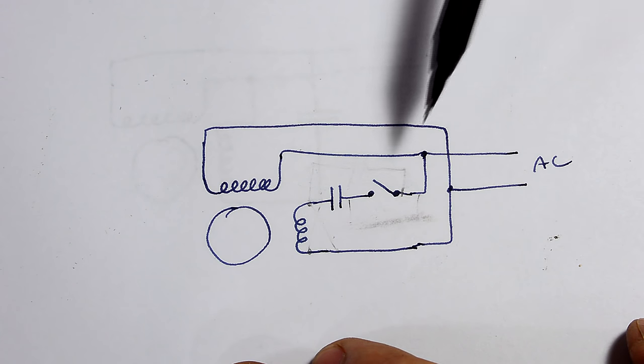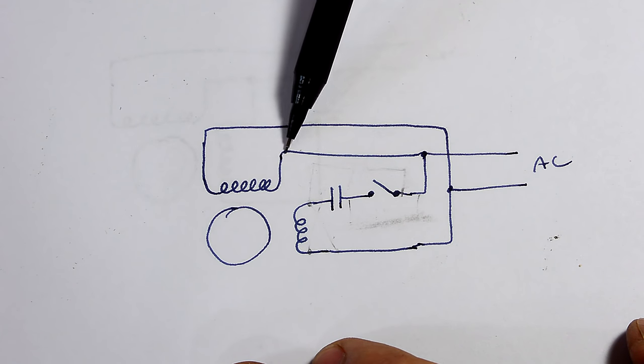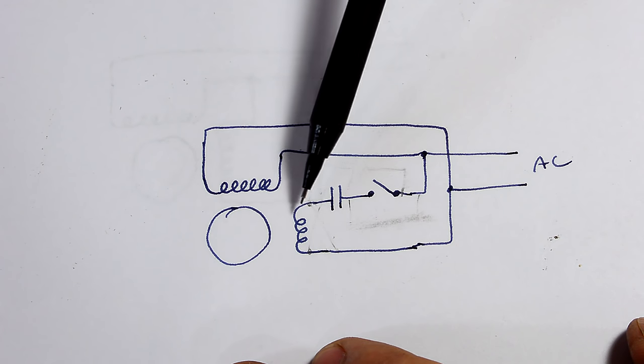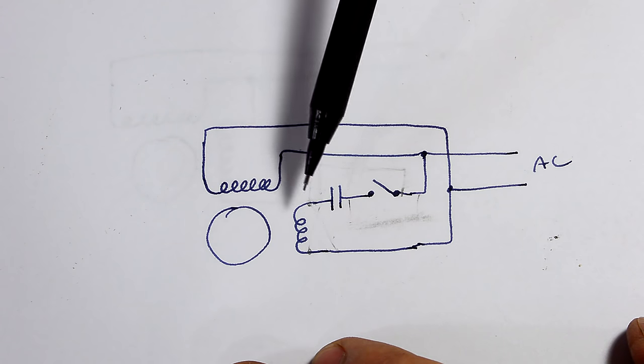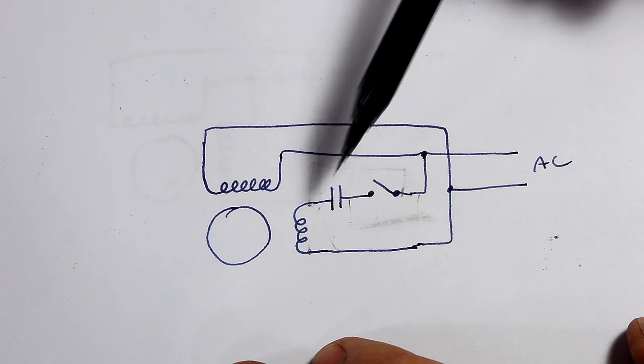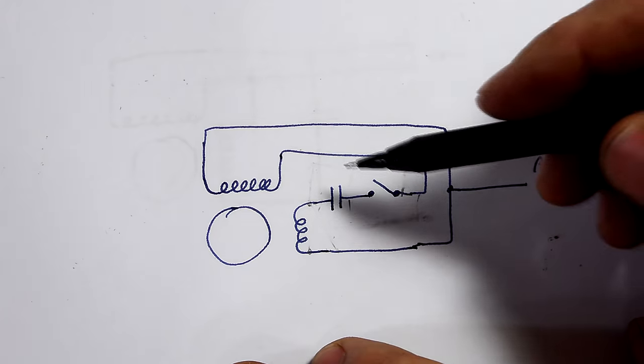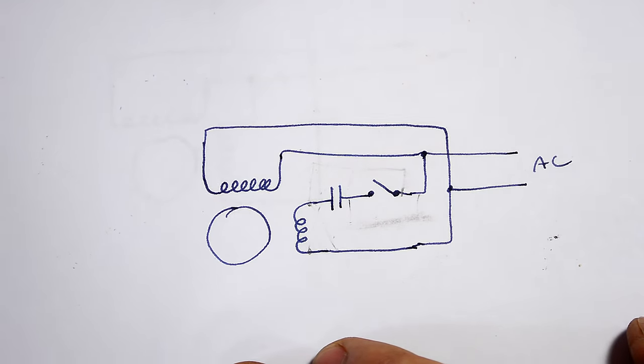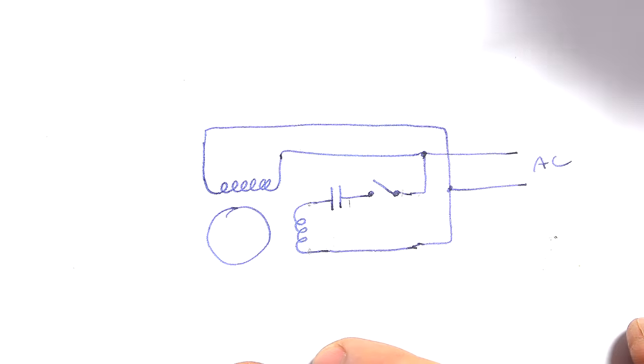So how do we reverse this motor? I can't just move the AC power connection from here to here. That would reverse the motor but that would make the starter winding the main winding and they're very different and that's not going to work very well. What we need to do instead is just to reverse one of these windings so that essentially we make a mirror image of the magnetic field and anything that was clockwise becomes counterclockwise.